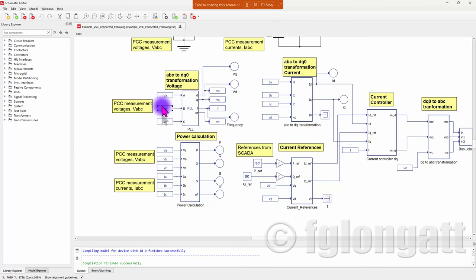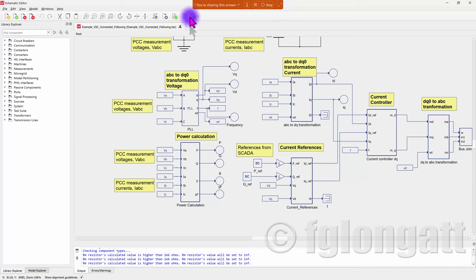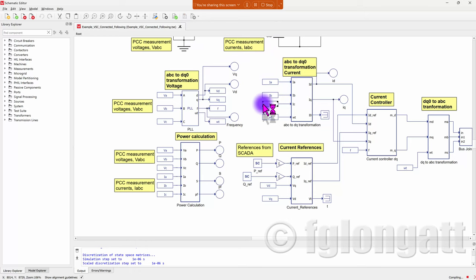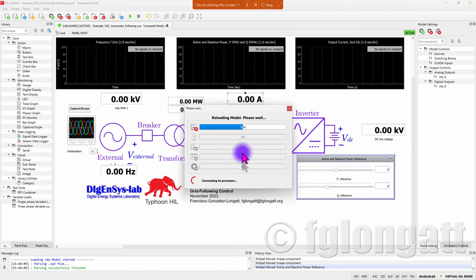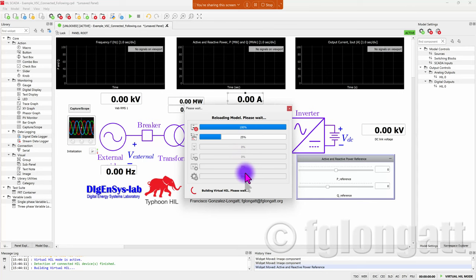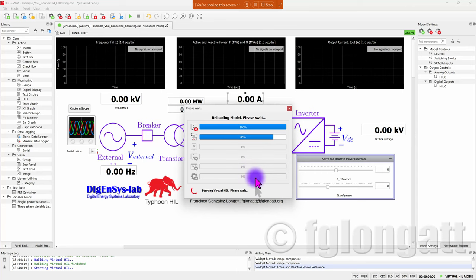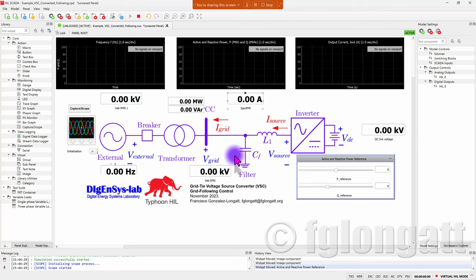The control is realized using DQ zero reference frame. Initially we take voltage measurements from ABC and convert them to DQ; we do the same with the currents and then go to a current controller. The references for those current controllers come from the power calculation. I am compiling this model and after compilation I will be able to run the simulation using the Typhoon HIL SCADA. Let me now open the SCADA. Right now we are loading the model inside the real-time simulator.